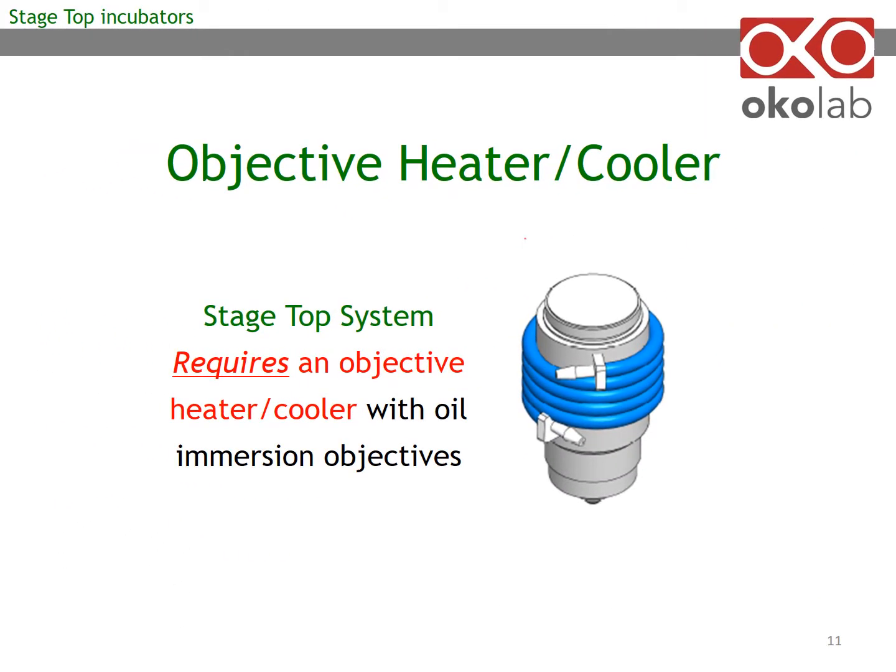If you are using an oil immersion objective, you have to use an objective heater cooler. It is represented by the blue tubing coiled around the objective. Cooling or heating liquid flows into it.